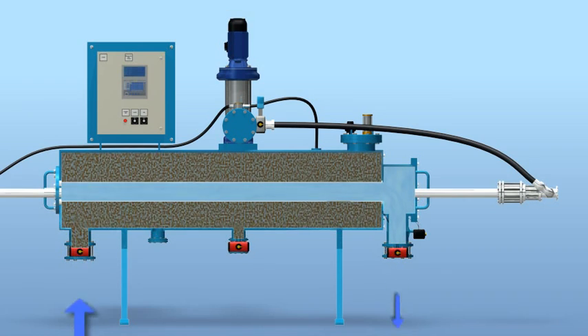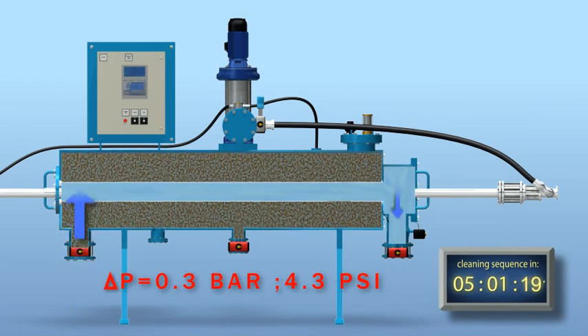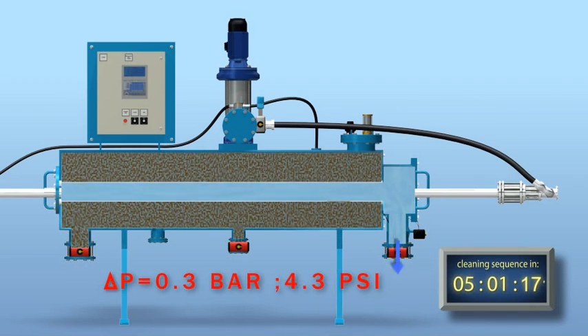The filter cake and the trapped suspended solids gradually increases filter differential pressure. The control system activates the self-cleaning sequence at a preset pressure differential level, or by a preset timer, whichever comes first.